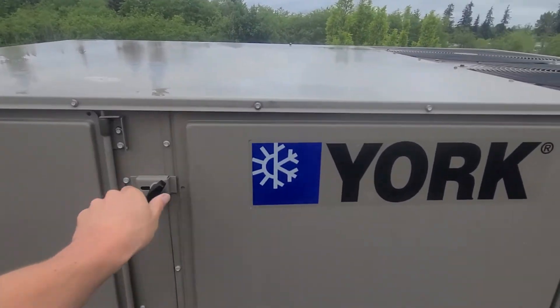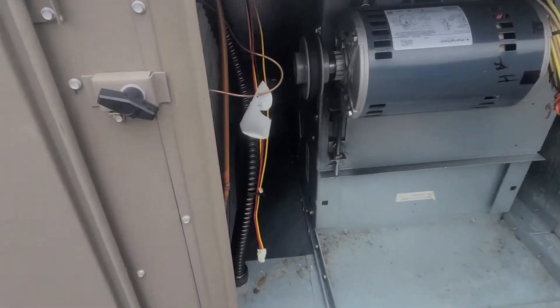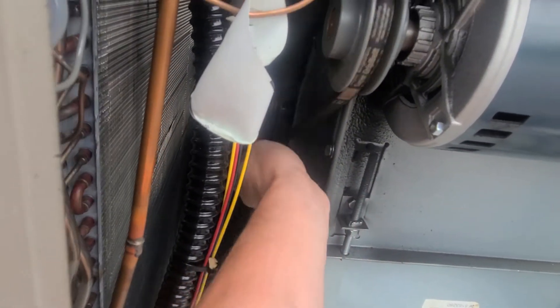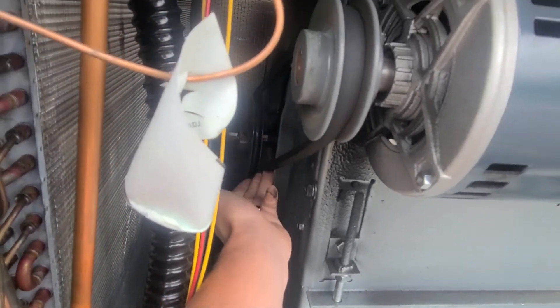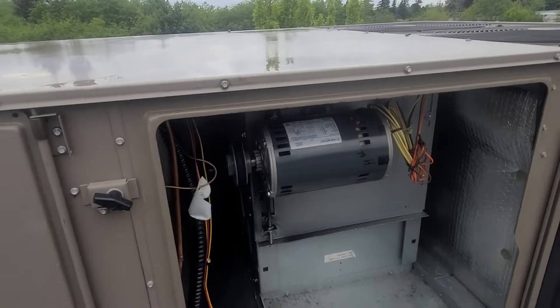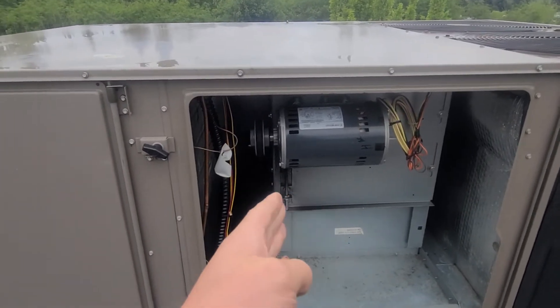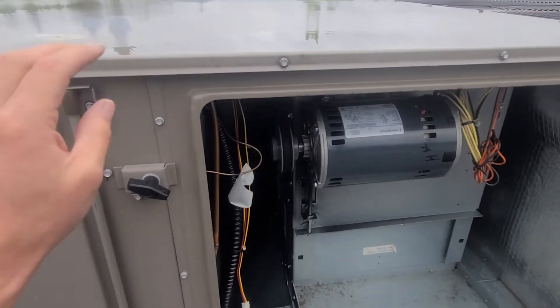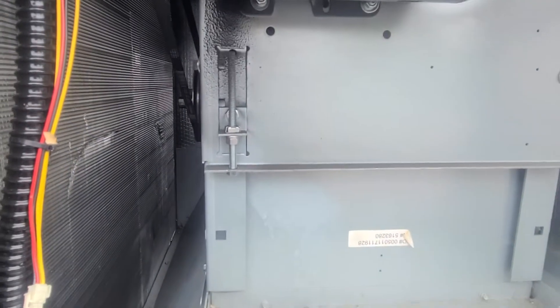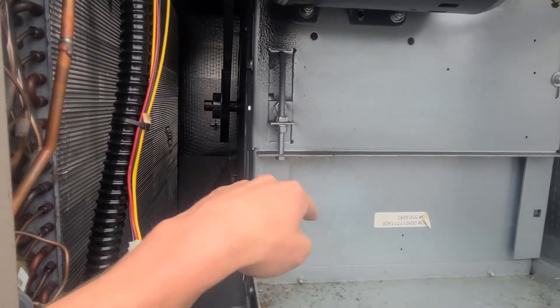Since I'm out here, I was also checking this belt, and I can see it's been rubbing quite a bit — there's belt dust and it's just super loose when it's running. I would usually check for grooves on the motor sheave, but there weren't any, so it might just be slightly out of alignment, and that's what's causing the extra wear on the belt.